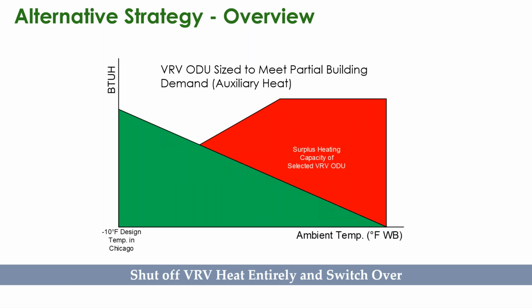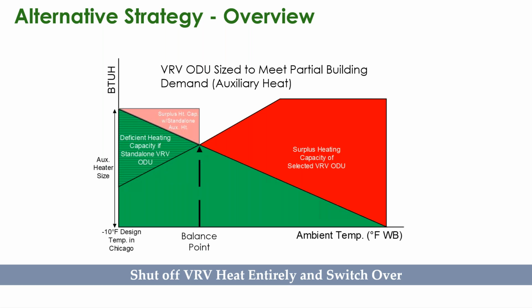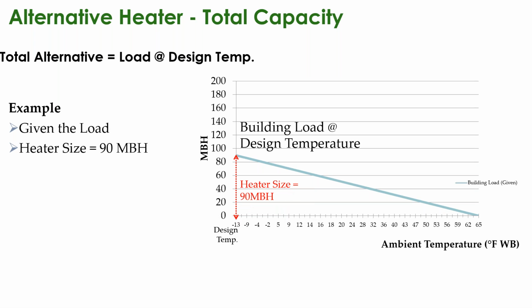Again, looking at that same load profile, you have surplus heating capacity of the VRV all the way down to your balance point. As that point crosses, you have a deficit of capacity if you were to stay with the standalone VRV system. Beyond your balance point, you're going to size your auxiliary heater to be able to handle the entire heat load all the way down to your design condition. That way, if there is a failure, the system is already entirely switched over, either on the failure or at your predetermined temperature point, your balance point.